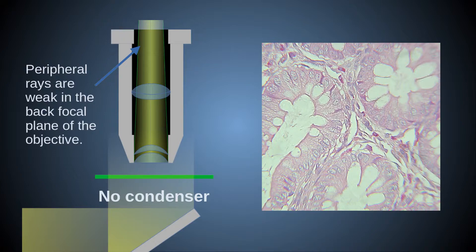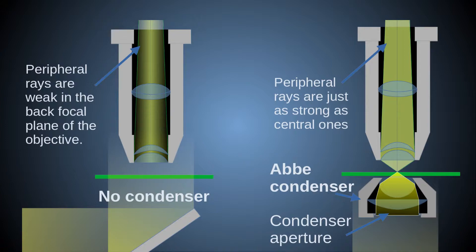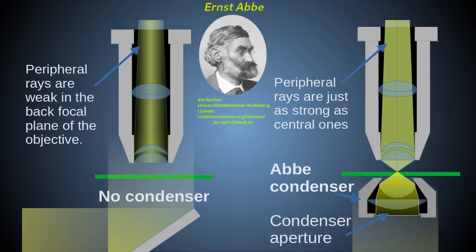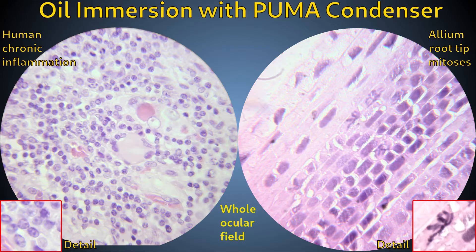A reliable way to concentrate the incoming light into a wide-angled cone beam is by means of a two-lens condenser system originally devised by Ernst Abbe at around 1870. The open-source Puma system has its own version of an Abbe condenser with a numerical aperture of about 0.938. The Puma condenser can also be oiled for use with oil-immersion objectives, allowing for a useful magnification of up to a thousand times when used with a 10x eyepiece.